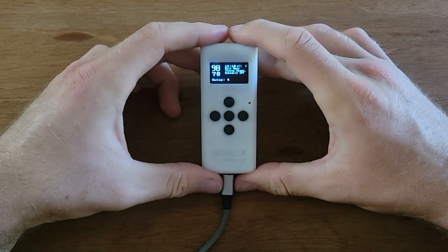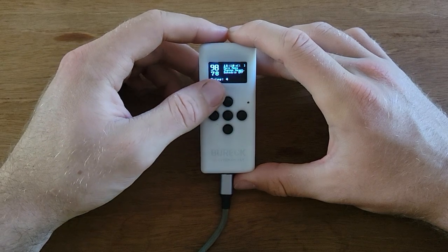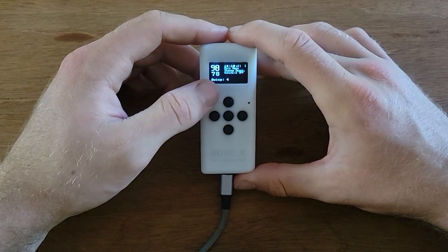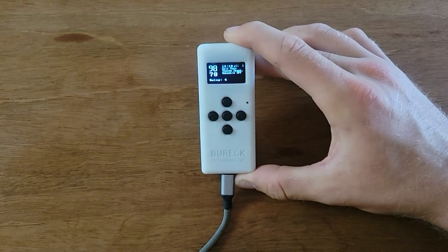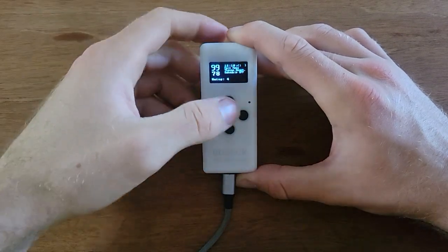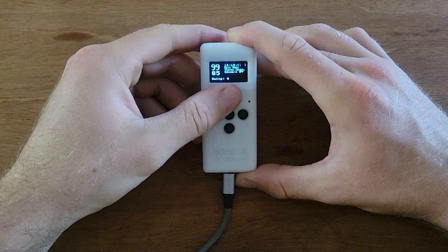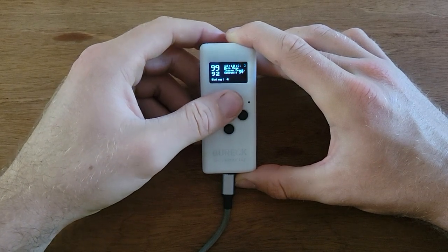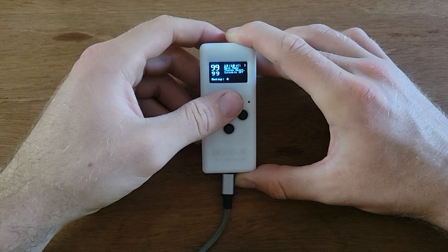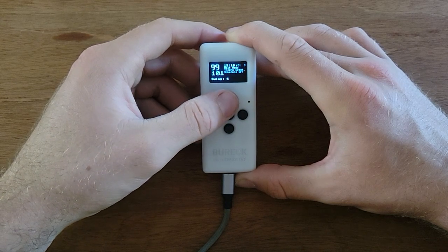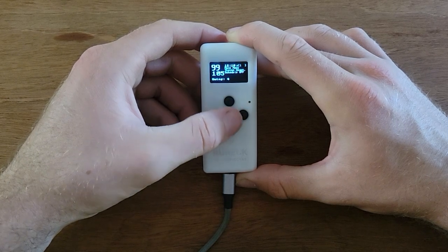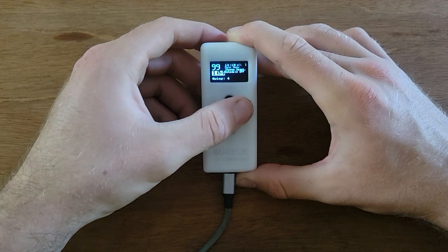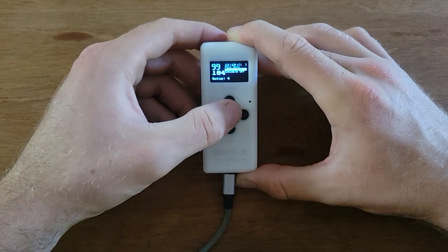So going over the rest of the things on the main menu here, swing is probably the most important feature. To start with, what swing does is it's the difference in temperature that will activate and deactivate your heater. So right now you can see if I change the set temperature up to 99, nothing happens. Nothing happens when I hit 100, 101, 102, 103, and then once I hit 104, it's because I have the thermostat deactivated.